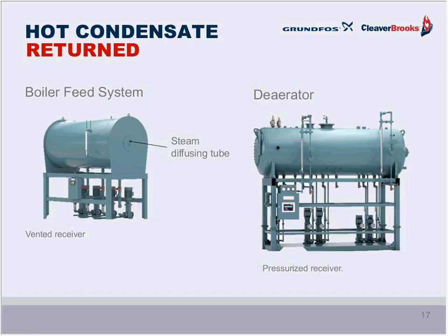Now on this slide, you see a vented receiver on the left with a steam diffusing tube used to heat the water to as close to boiling as possible to give off some of the oxygen. But that is not really enough to do the greater part of the job, as the temperature in the tank normally doesn't get much over 180 degrees, leaving much of the free oxygen in the water.